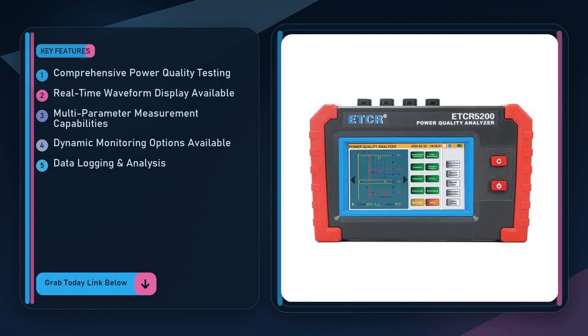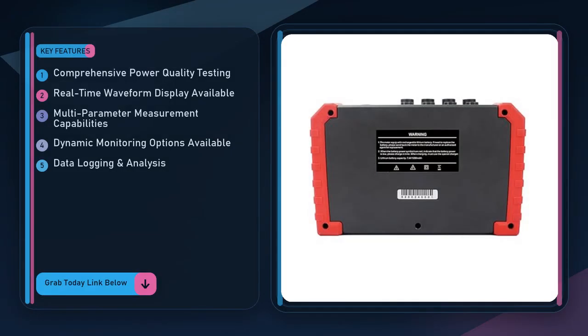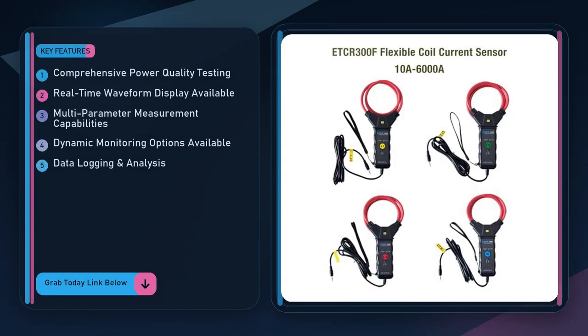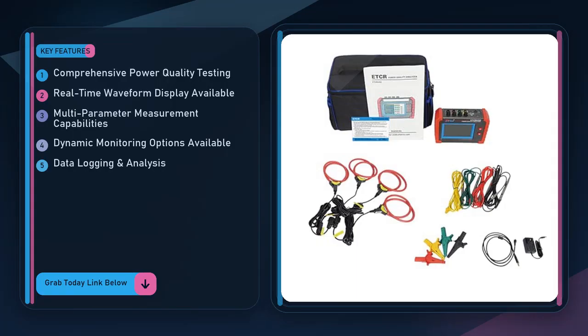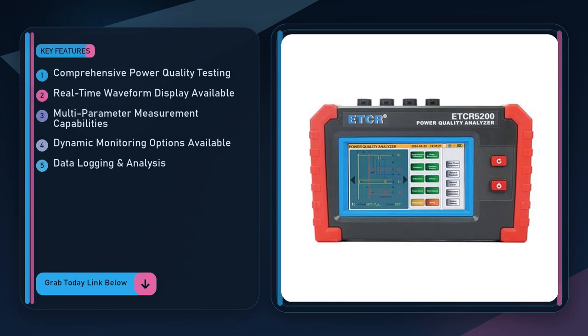The real-time display is not just a pretty graph. It lets you spot a sudden voltage sag the moment a motor starts, see the ripple that a poorly filtered inverter introduces, and watch how the system recovers. For a maintenance engineer who needs to convince management that a line conditioner is worth the expense, that visual evidence can be the difference between a budget approval and a dead end.